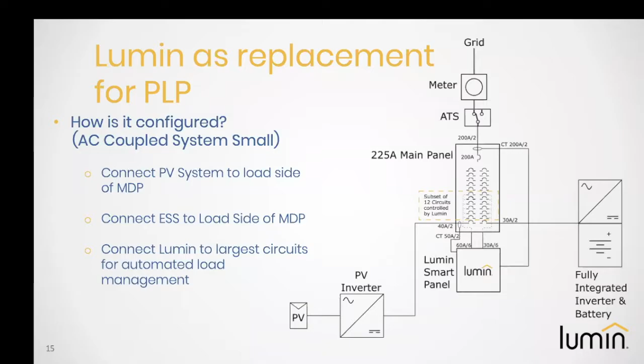The primary difference between this particular design and the previous one is that, due to the larger output of the PV and the battery, they're now being combined in this combiner panel or generation panel before interconnecting on the load side of the automatic transfer switch. So we can see our generation panel here, and then we can see that single output coming in to either a terminal or an adequate position inside of this ATS or MDP to make for that connection.